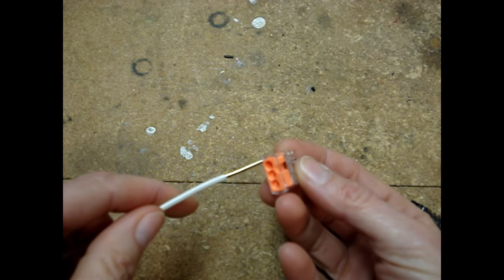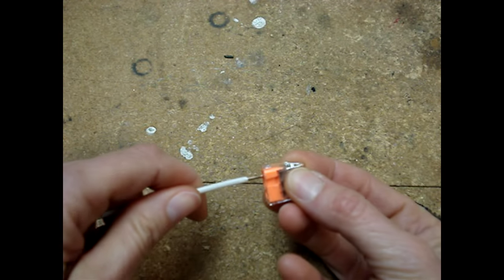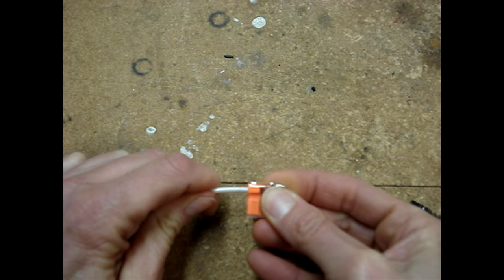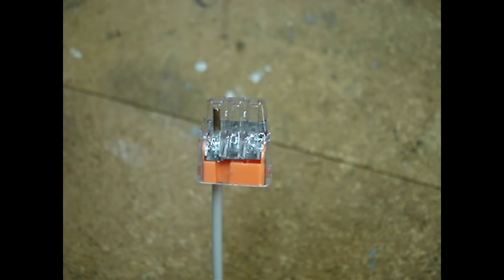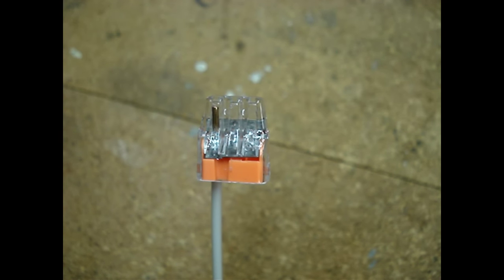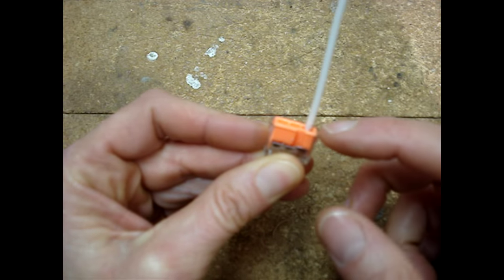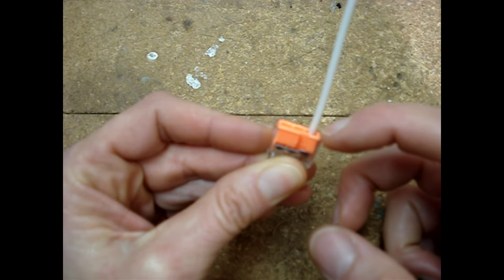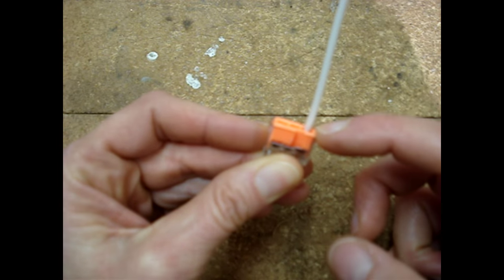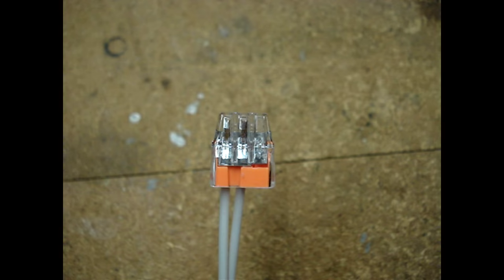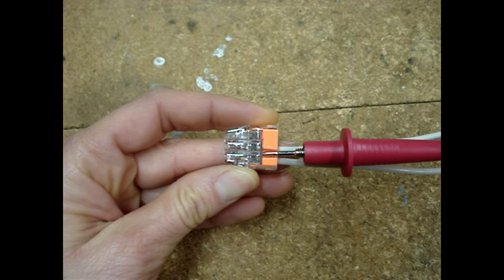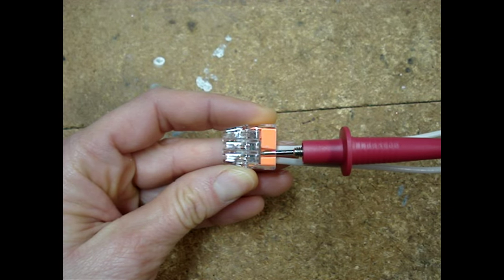Then push the wire into one of the ports. If the wires strip back correctly and are inserted fully, you'll see the tip of the wire at the end of the clear window. And there shouldn't be any copper showing beyond the back edge of the connector. Use only 1 wire per port. There's an additional port that you can put a probe from a multimeter into.